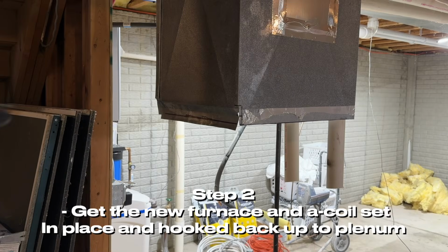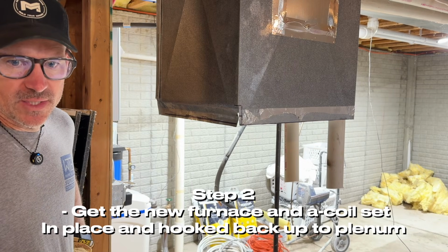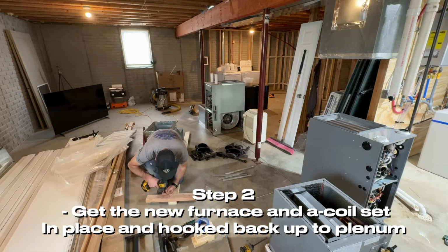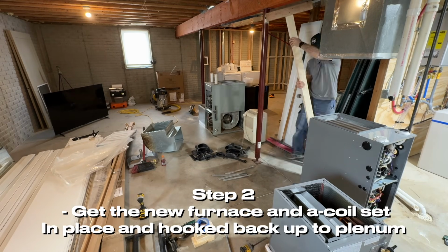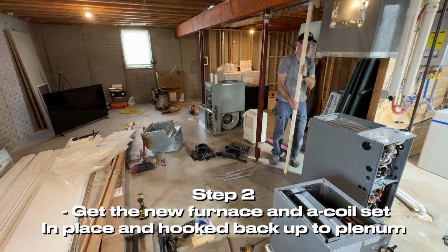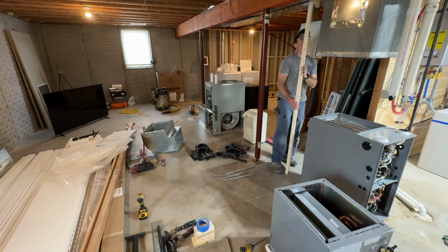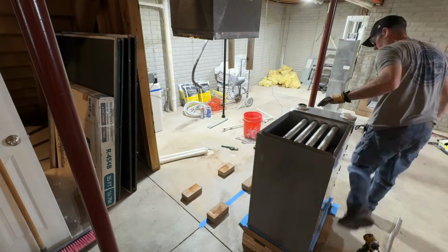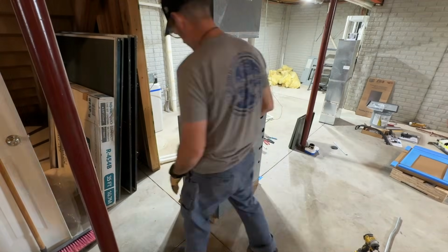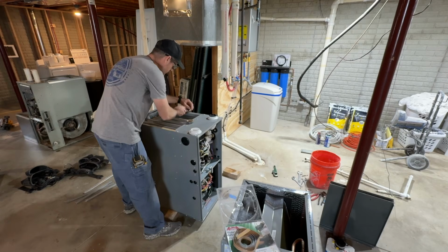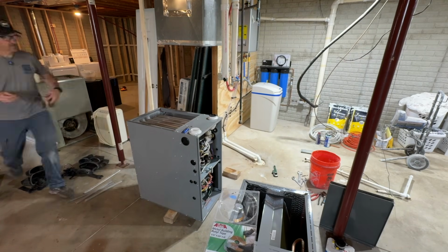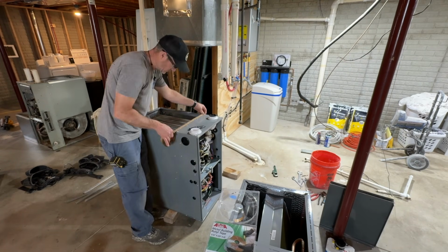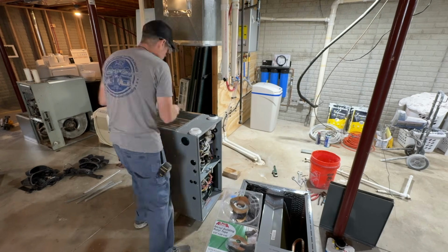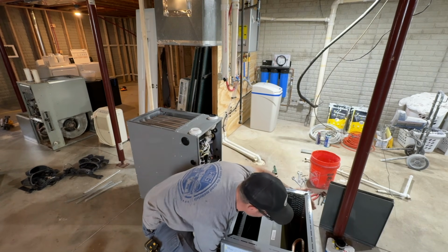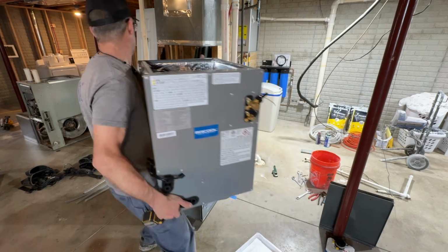All right, so now we got that close. Go ahead and try to get this plenum, or this A-coil, on there. I don't think I can move it all at once, so I've got to figure out how to jack this up. I might have to get a jack and a 2x4 to push this up. This part took a little more planning than I expected. The new furnace and A-coil was about 1.25 inches taller than the old one, so I had to cut up the plenum and then downsize it about 1 inch, 1.5 inches to get it to line up with the new A-coil. This is where 2 people would come in handy.